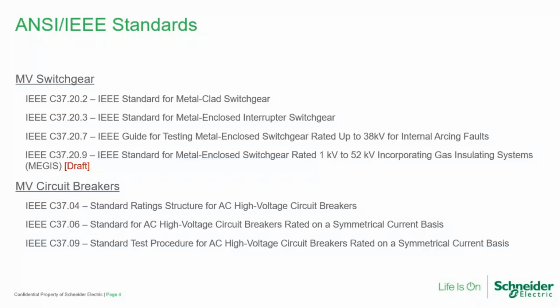And then looking forward a little bit, I think it's important for me to introduce this new standard that's in the draft stage right now that the IEEE standards committees are working on, C37.20.9, which is the IEEE standard for incorporating gas insulating systems into metal enclosed switchgear. It's been in the draft stage for several years and is still being worked on, and will soon be the standard which all of the gas insulated switchgear, at least for medium voltage applications in the US, will need to be designed and tested and rated according to. So keep an eye out for that newer standard that should be released, I would say, probably within the next couple of years.